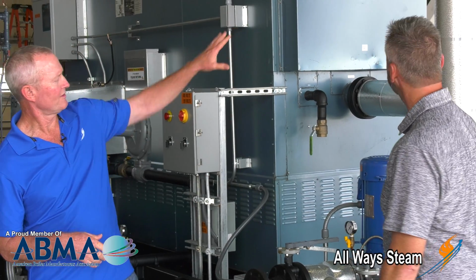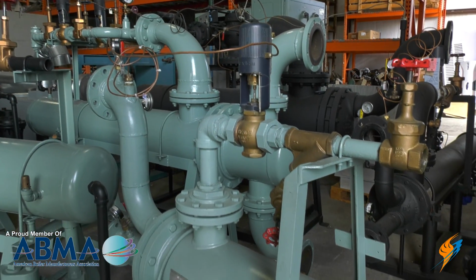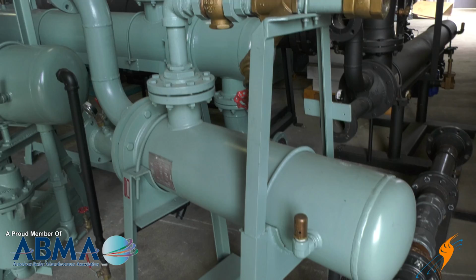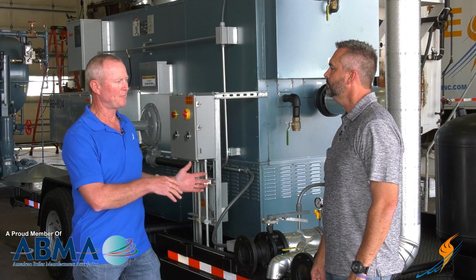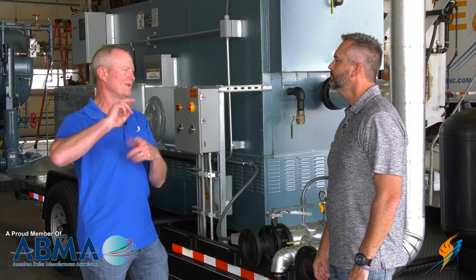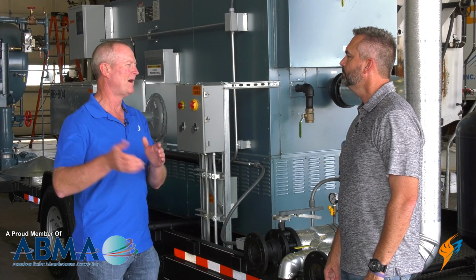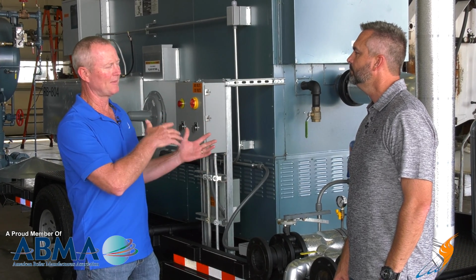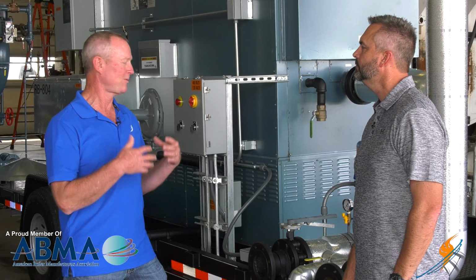Typically, like one of the trailer units over here, we would take a packaged shell and tube heat exchanger, slide it in that unit. When they get to the job site, they'd pull it out, take it to their source, run steam to it, condensate back, and give them hot water. That way we can use that steam unit combination for steam or hot water, and that's worked really well over the years.